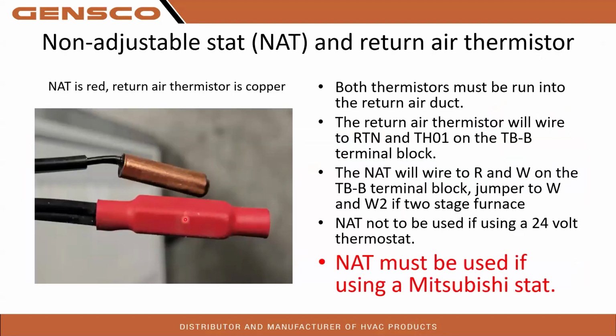This is a non-adjustable thermostat set for 65 degrees. Both of these will run into the return air. The return air thermistor will wire into RTN TH01 on the TBB terminal block. That's the copper one. Remember, copper is the thermistor, red is your non-adjustable stat. The non-adjustable stat, I'll have some pictures of this coming up soon, is going to wire into the TBB terminal block between R and W. And if you have a two-stage gas furnace, you're going to put a jumper between W and W2.